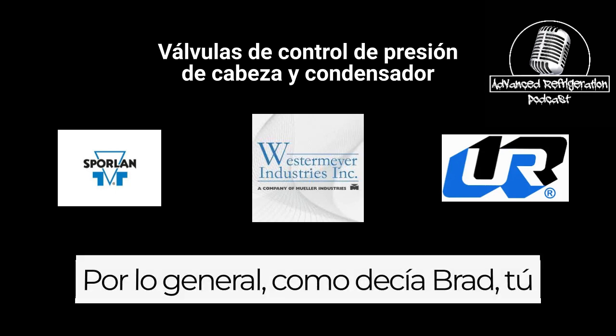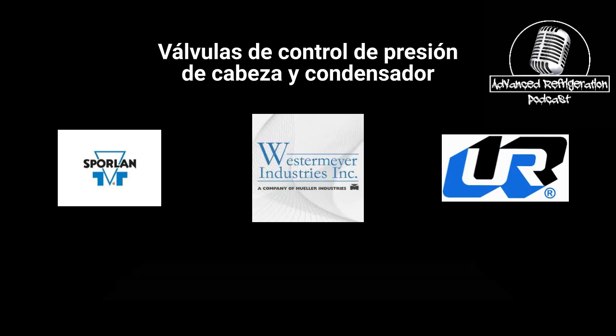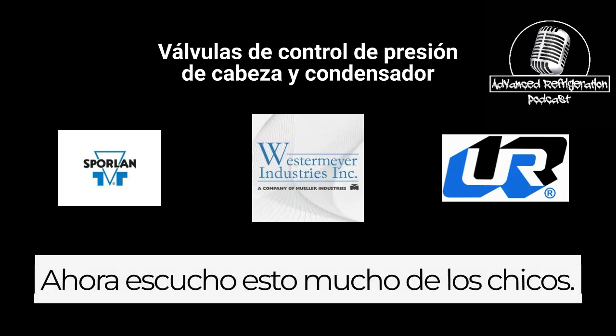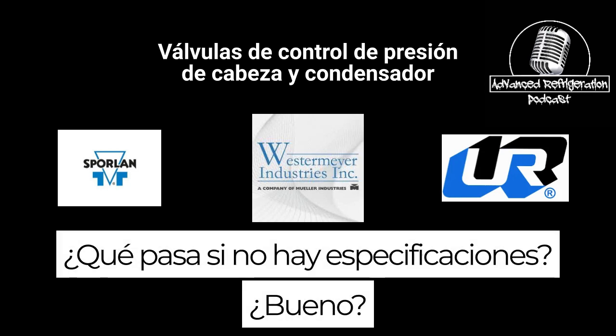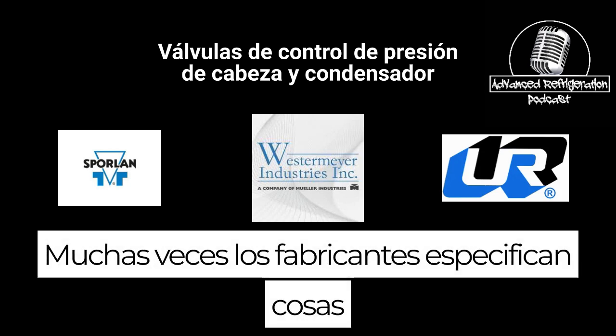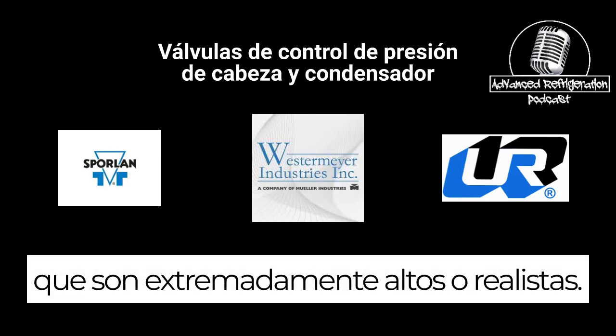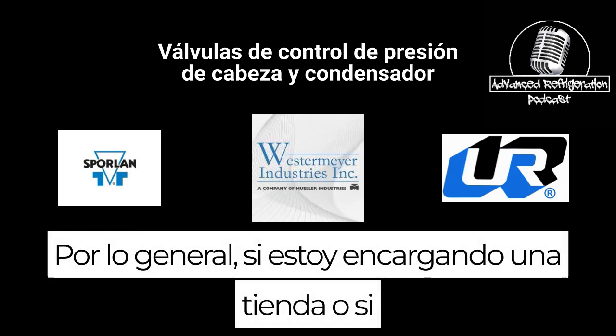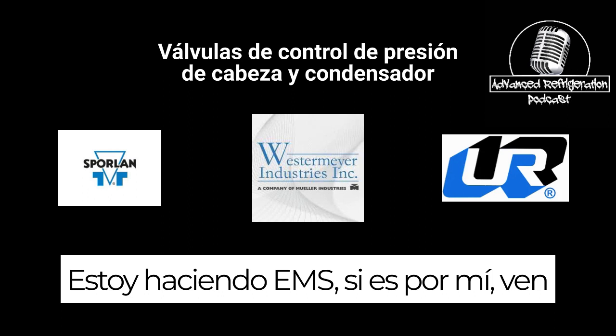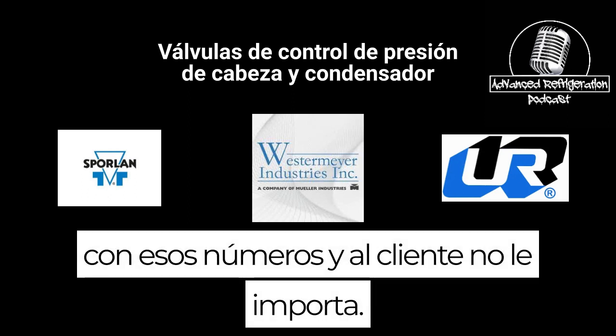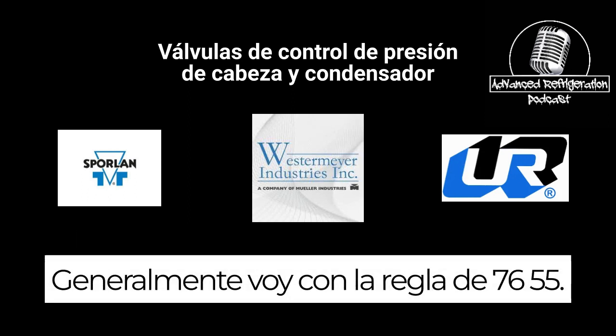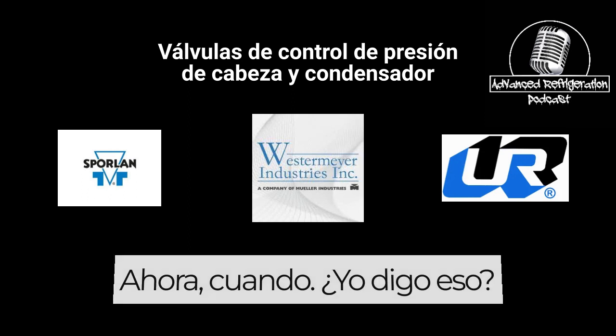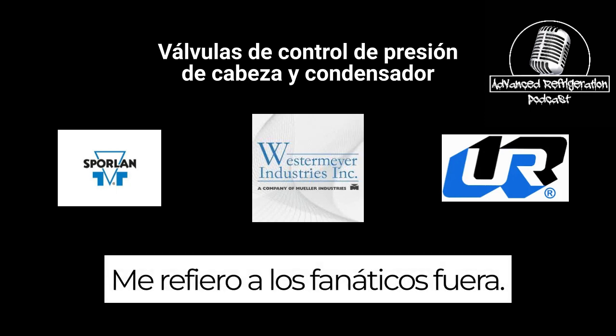Yeah. So generally, like Brad was saying, you always want to run customer spec. Now, I hear this a lot from guys: what if there is no spec? A lot of times manufacturers spec things that are extremely high or unrealistic. So if I'm commissioning a store, doing EMS, and it's up to me to come up with those numbers and the customer doesn't care, I generally go with the rule of 76-55.